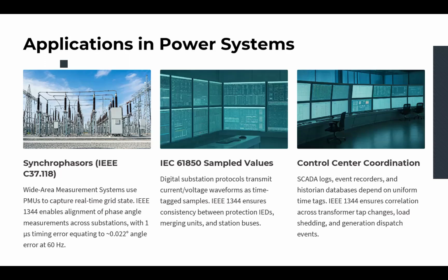Another aspect is IEC 61850 sampled values and digital substations. In such a system, traditional analog CT or PT, current transformer or potential transformer, signals are replaced by sampled values. They are digitized, time tagged, and transmitted over the Ethernet-based process bus. So the merging unit that performs the digitization must sample and transmit the waveform at exactly the same time, within tens or hundreds of nanoseconds.